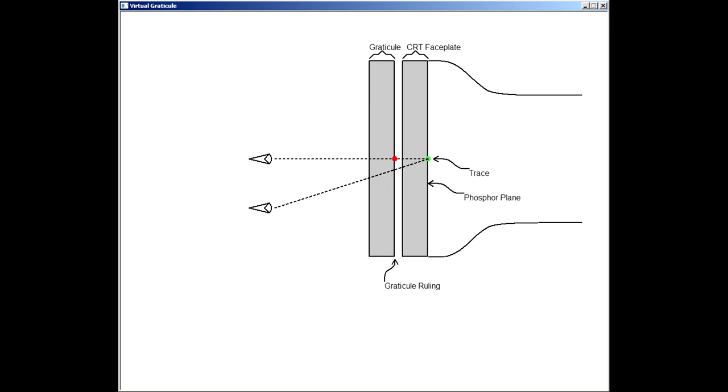Some space is shown between the graticule and CRT faceplate for clarity. This space would normally be as small as possible to minimize but not eliminate the parallax error.